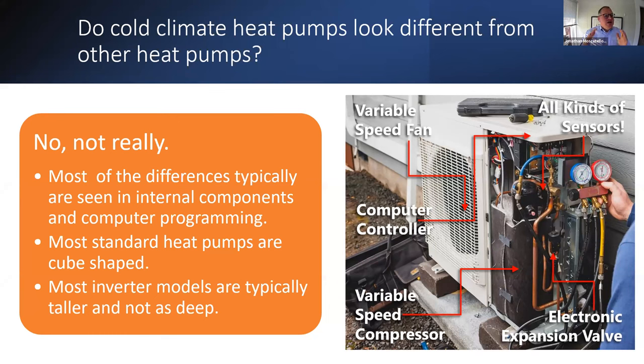Now, because the heritage, the technology came from Asia to begin with and Japan really to start with, they are small compact units that are what we call side discharge. And whereas in America, most air conditioners and heat pumps are cube shaped and rather large, we have more space and it's just what we had developed technologically over time. So cold climate heat pumps, really, you might have two side discharge machines and they wouldn't know if one was cold climate or the other, except for maybe some branding on the outside.